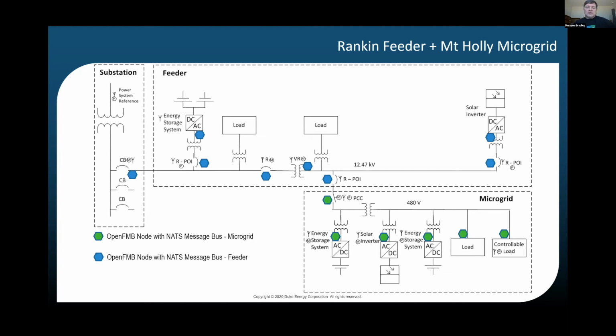So one of the things we'll have to do is build that bridge connectivity between both of those NATS buses. We have to be careful how we architect that, because the microgrid may be a customer-owned piece of setup, so from the feeder level we may have no visibility into the actual components inside the microgrid. We have to know the capabilities of the microgrid as a whole and give it rules for operations. So we plan on making that connectivity between those two buses.